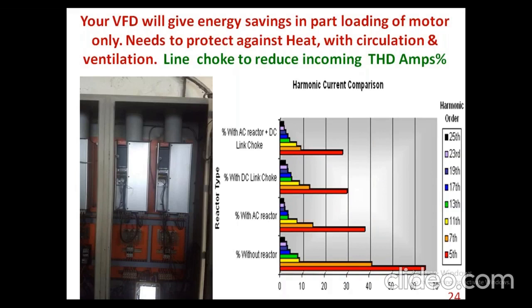Now, one energy saving option there is, instead of having a 75 kilowatt compressor, as an energy auditor, we can suggest the textile industry to replace that 75 kilowatt with a 90 kilowatt, straight away bringing down the kilowatt loading of the given machine. Instead of 110% at a 1.2 service factor, you can bring it to 80 or 90%.